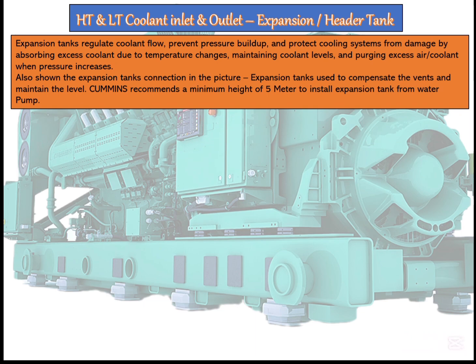Let's look at the expansion tanks. Expansion tanks are used to regulate the coolant flow, prevent pressure buildup, and protect the cooling system from damage by absorbing excess coolant due to temperature changes, and to maintain the coolant level, venting excess air in the system into the air.